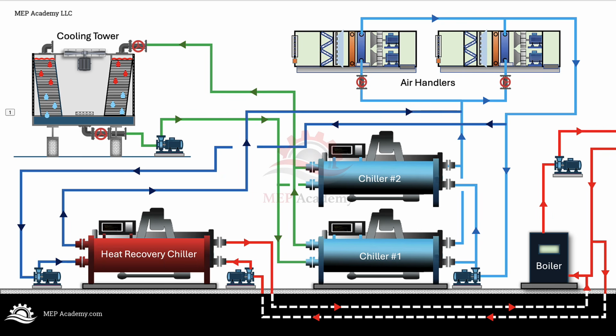A good example is an office building with interior zones that need cooling even during mild or cool weather. Interior spaces can stay warm because they are surrounded by other conditioned spaces and filled with people, lighting, computers, and equipment. At the same time, the perimeter zones may need heating because they are exposed to outdoor conditions. A heat recovery chiller can remove heat from the interior zones and deliver that heat to the perimeter heating system or reheat coils. The system is not creating heat from nothing. It is moving heat from where it is not wanted to where it is needed.